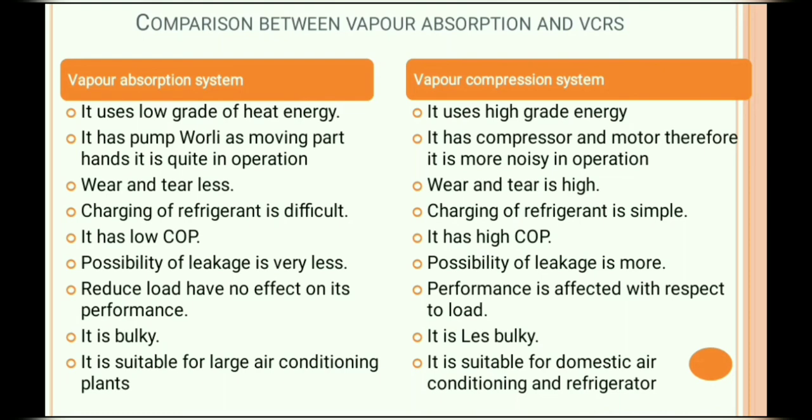Okay, if we talk about the effect on performance with respect to the load. In the VCRS, there is a much greater effect with respect to the load. Once we change the load, the performance of the system also changes. But in the vapor absorption system, once we change the load, the performance of the system does not change. That means the reduced load has no effect on the performance.